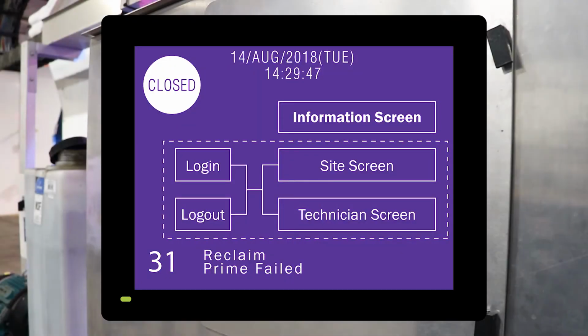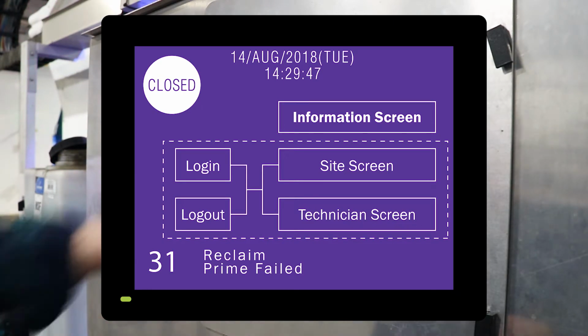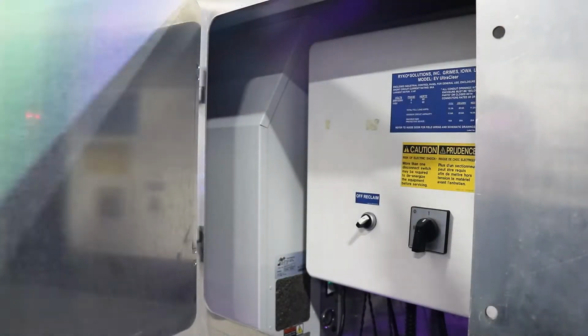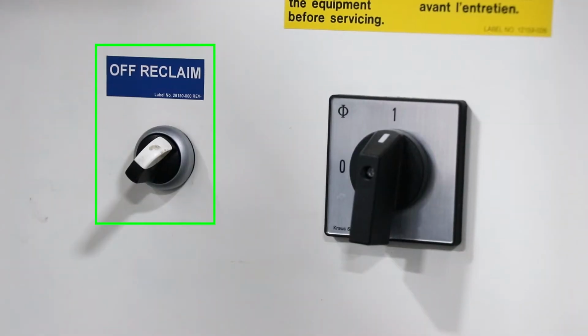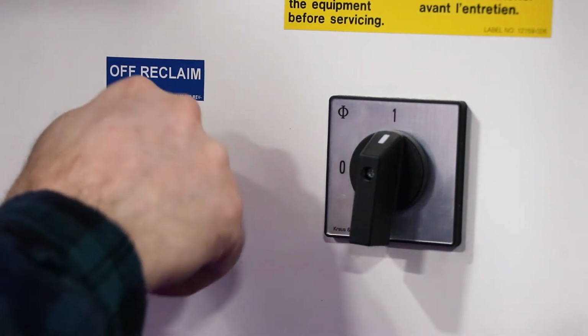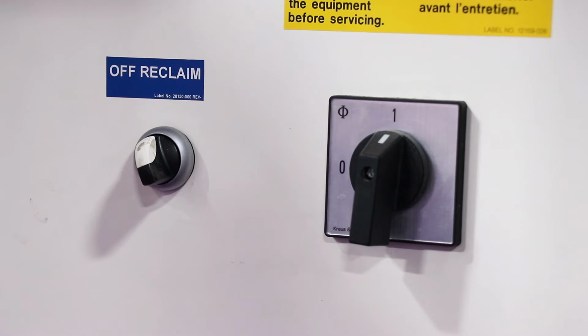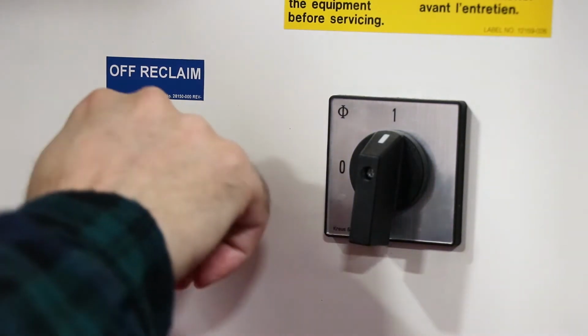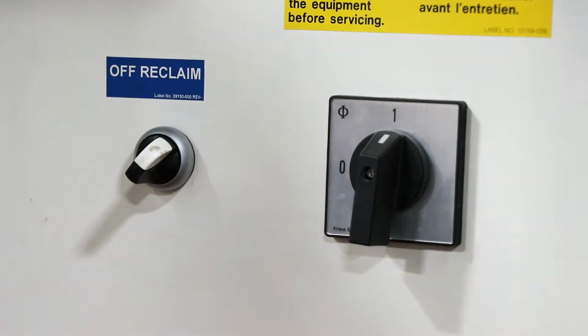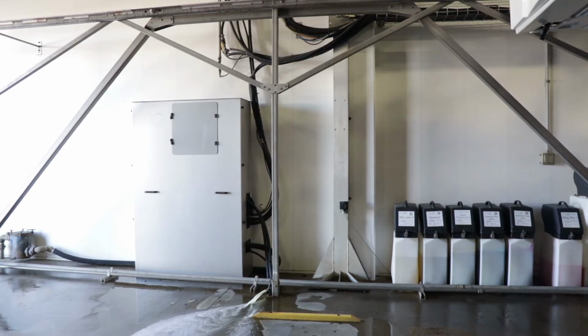Here we see code 31, reclaim prime failed. Go to the reclaim unit and look for the off reclaim switch. When reclaim fails, it may still be in the on position, which is tilted to the right 45 degrees. If so, then turn it off, wait a few seconds, and turn it back on. It will attempt to prime 5 times. If the problem persists, call for service.